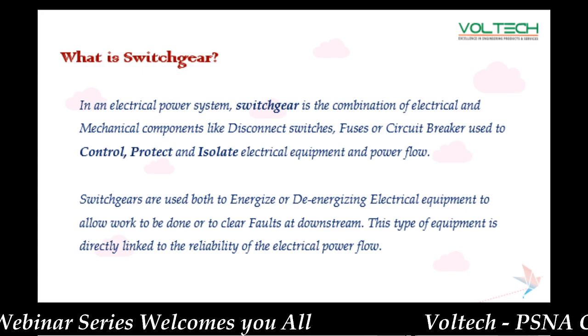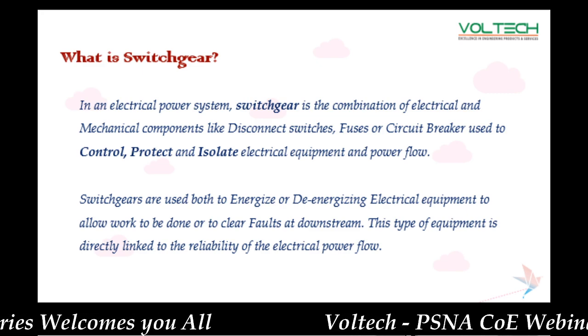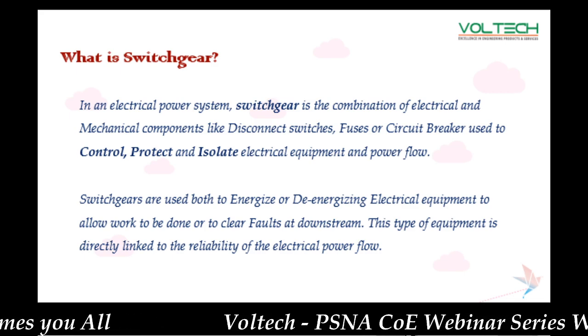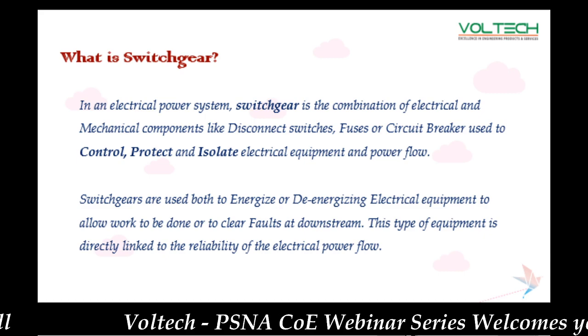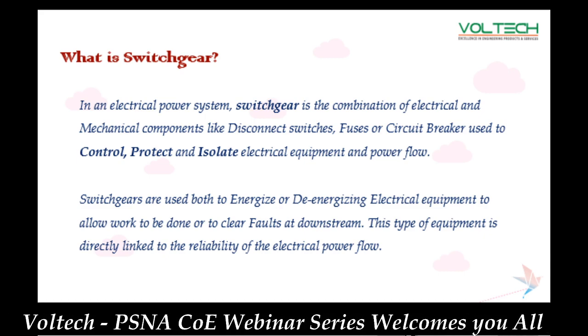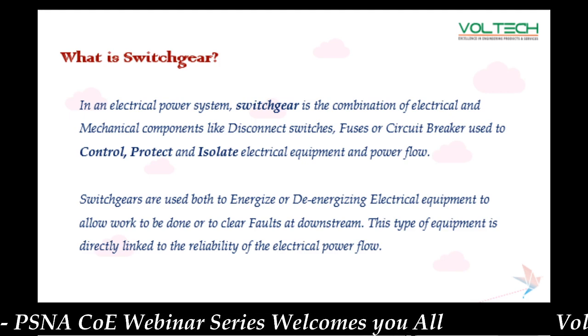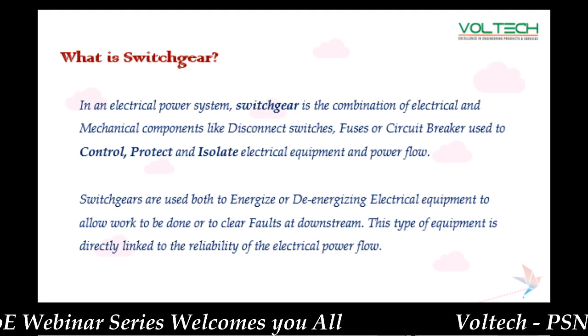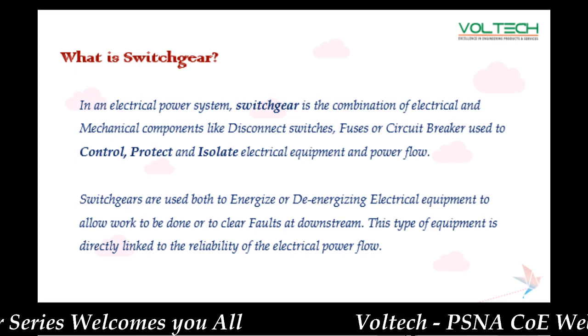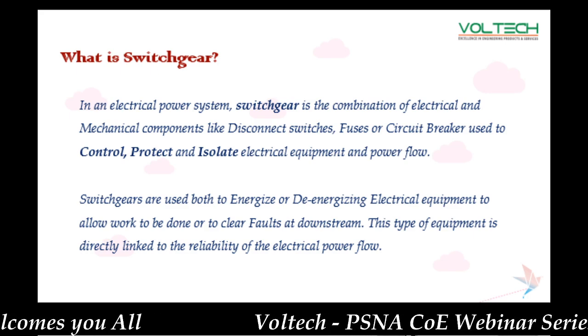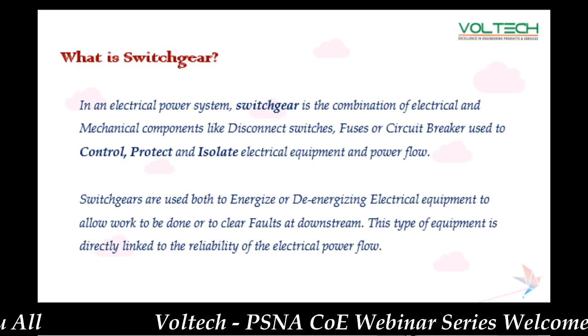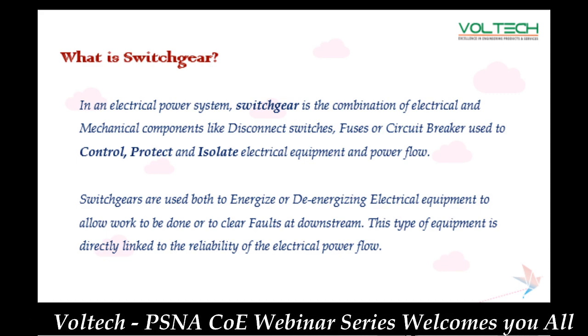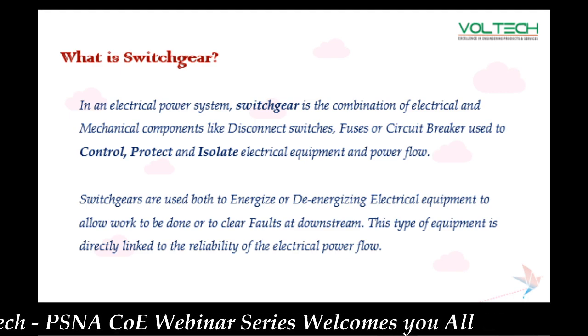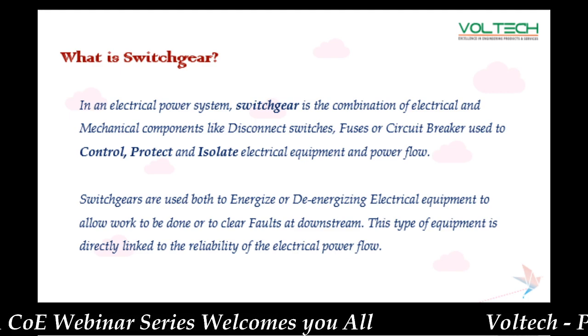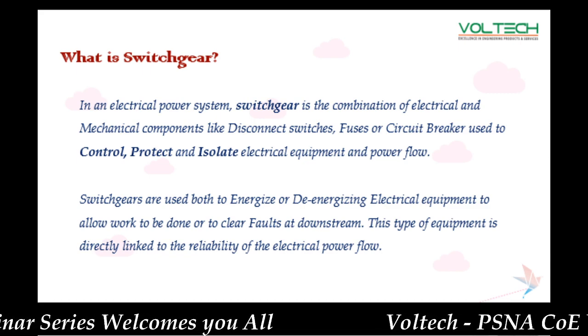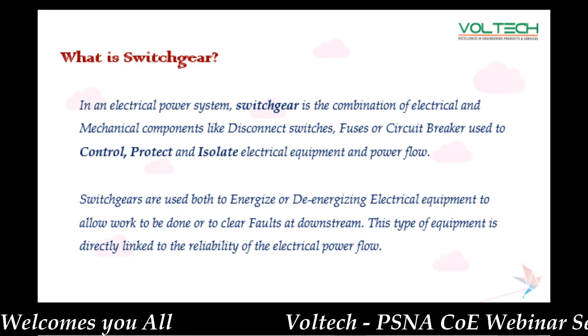First, let's talk about switchgear. Switchgear is a compartment with mechanical and electrical components to do switching operations or isolate during a fault, organized by the protection relays. This switchgear is placed mostly at the medium kV and lower kV levels. If you go to higher kV, the switchgear is removed, and in its place we use outdoor equipment like isolators and breakers. So switchgear is a basic concept to understand power flow, how faults are detected, and how they isolate the power flow.